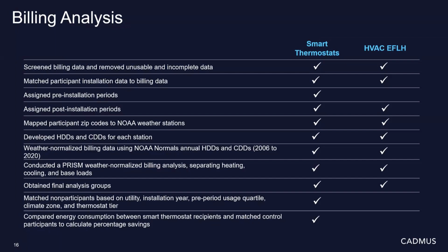For the thermostat billing analysis, we assigned annual pre- and post-installation periods. For the EFLH analysis, we assigned only the post period, which would be the year following the HVAC installation. Next, we mapped all the participant zip codes to the nearest NOAA weather station and matched in the heating degree days and cooling degree days for each station for each monthly billing period. Then we weather normalized the billing data using the Princeton scorekeeping method, also known as PRISM. This allows us to disaggregate the heating and cooling and baseload components of usage.